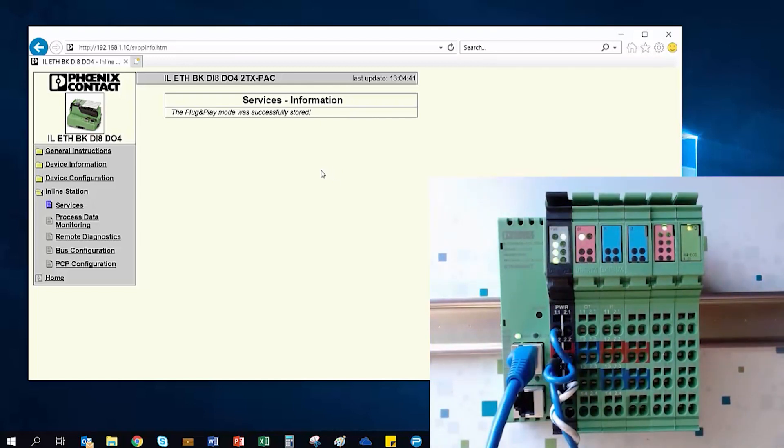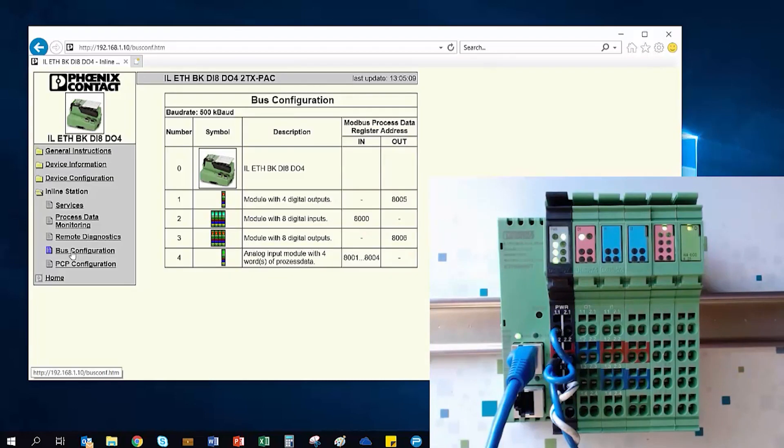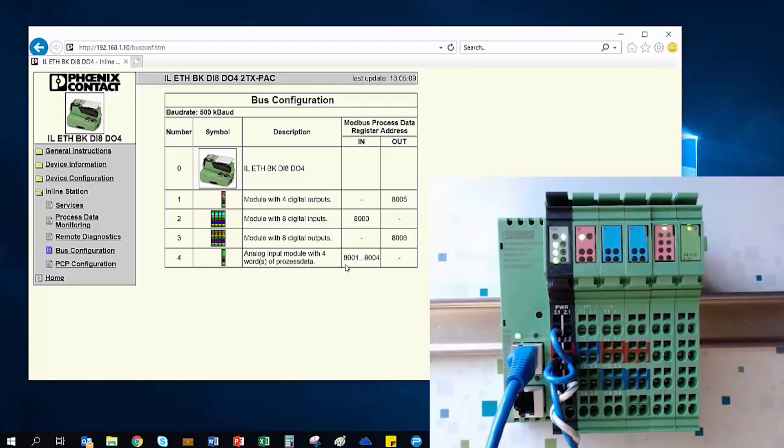While you already have the web page open, you may want to look under the Bus Configuration menu. This page gives you a representation of the I.O. on the local bus, but more importantly, it gives you the Modbus addresses you will want to access to read and write to the I.O. points via your Modbus Master.